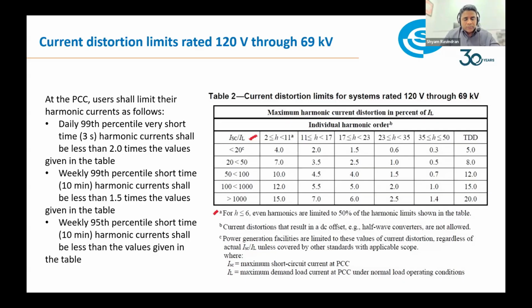And why do we have two definitions, daily and weekly? The same thing will be reported in the reporting format as well. We wanted to analyze both the short-term analysis as well as the averaging period analysis. So from a weekly perspective, on a 10-minute averaging period, on my 99th percentile, how does my total TDD work? That is something that is defined very clearly in the standard.